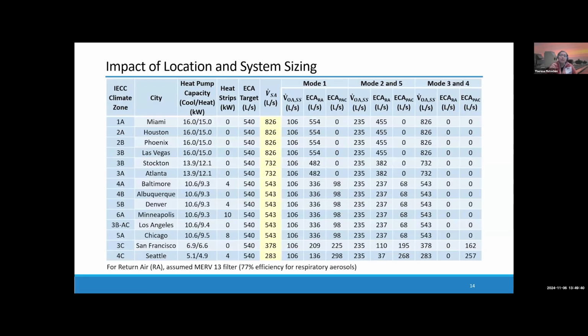There's a lot of information here, but I essentially want to make one important point. What I'm doing here is running models for 13 cities across the United States to look at the impact of this control system. What ends up happening is we design HVAC systems based on their cooling capacity. So for example, if we're in Miami, we have much higher supply flow rates out of our central HVAC systems than we would in San Francisco or Seattle, where the weather is more mild. And so essentially the answers change depending on where you are geographically.